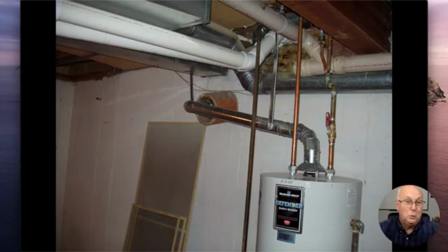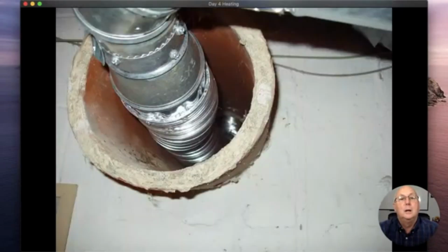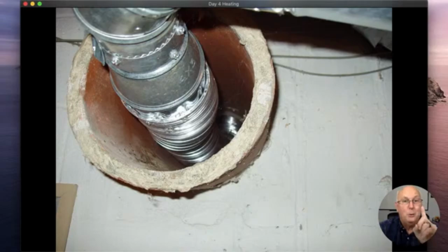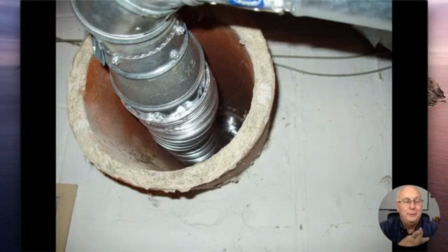Now, we can't use that big round clay tile for this many BTUs. So I think it's like a 3 or 4 inch vent connector that goes in there. Then that connects to a corrugated stainless steel. And I think the next slide shows it good. It really shouldn't even enlarge like it did here. They should use a smaller one so it's the same size going all the way up. But this is what's called a flue liner that goes through the chimney and all the way out through the top. All right. So every mid-efficiency furnace that goes into a chimney, every high efficient or every water heater that goes into the chimney by itself, they should all have flue liners.